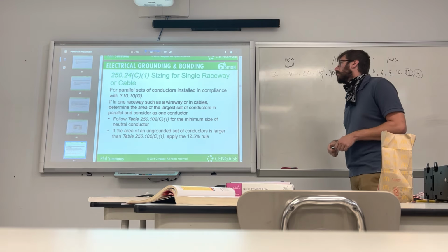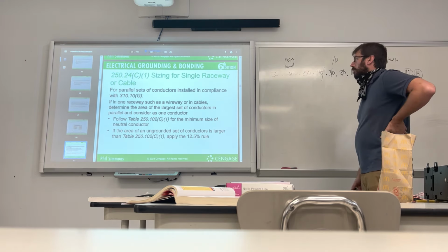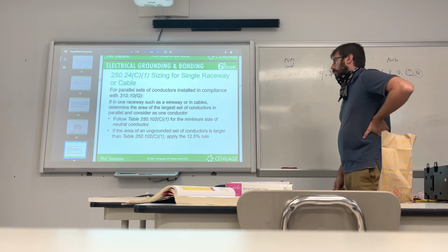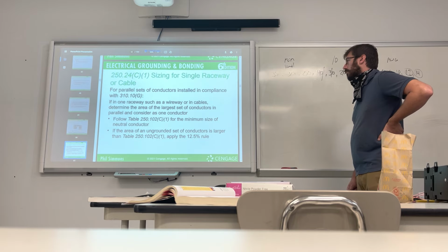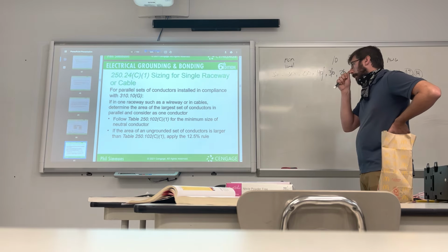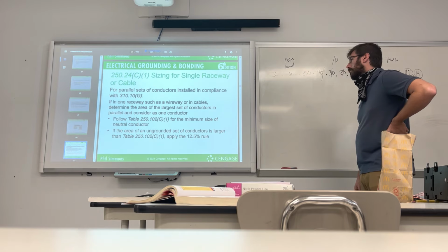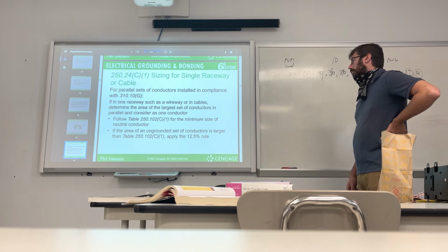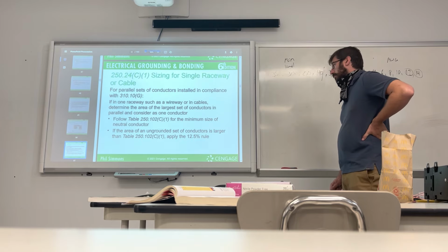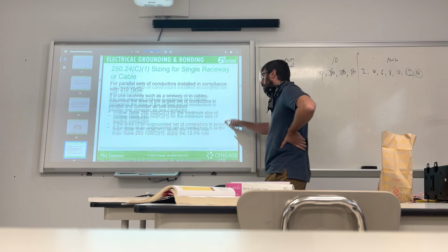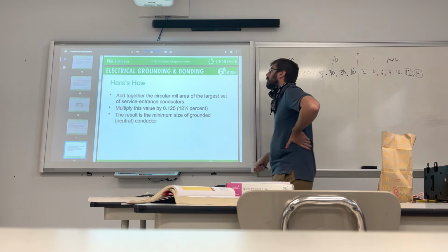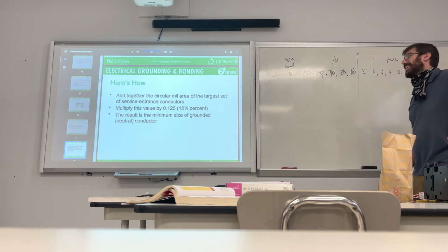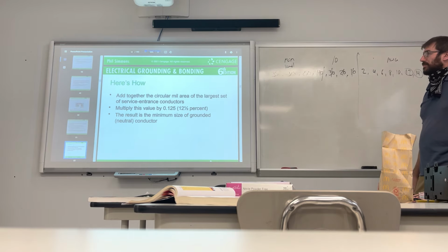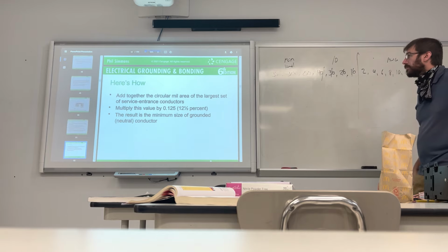Sizing for single raceway or cable. For parallel sets of conductors installed in compliance with 310, if in one raceway, such as a wireway, or in cables, determine the area of the largest set of conductors in parallel and consider it as one conductor. Follow Table 250 for the minimum size of neutral conductor. If the area of an ungrounded set of conductors is larger than Table 250, apply the 12.5% rule. Here's how. Add together the circular mil area of the largest set of service entrance conductors. Multiply this value by 0.125, 12.5%. The result is the minimum size of grounded neutral conductor.